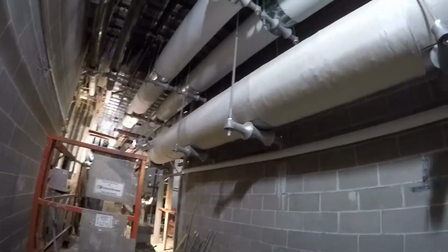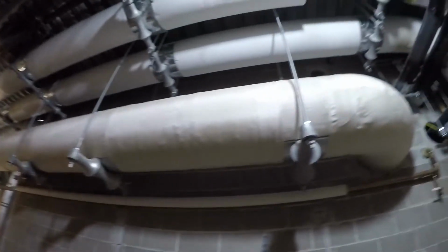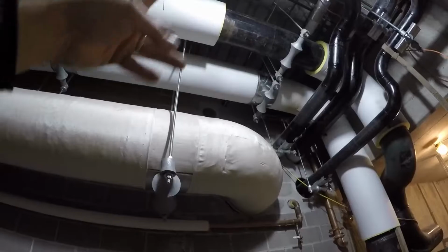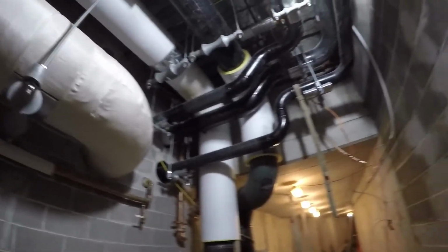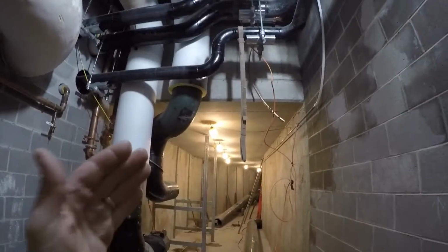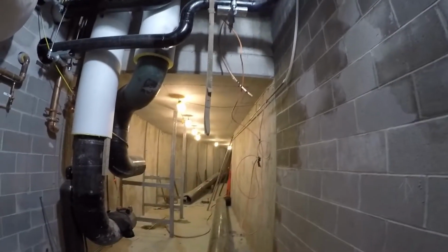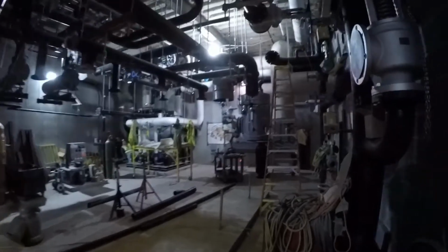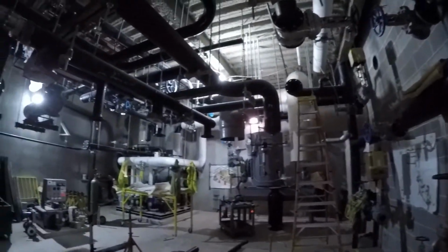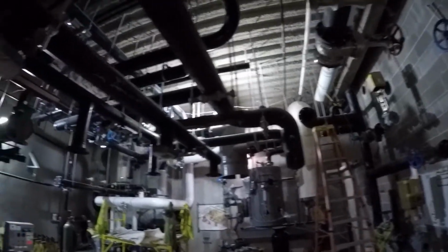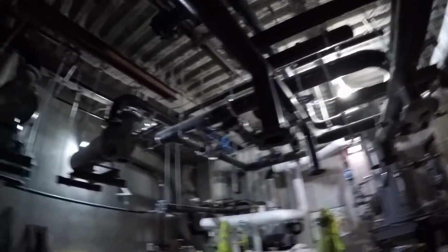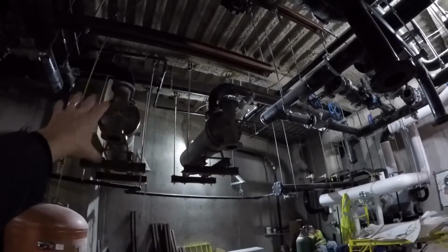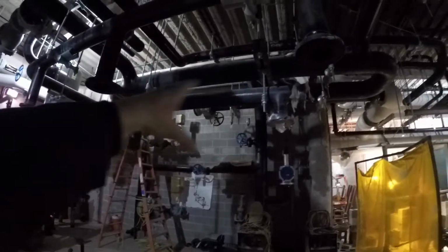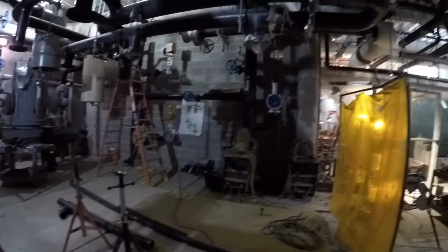Tunnel location in the basement. Looking at the mechanicals here, we have the chilled water supply and return highest up into the ceiling with the steam lines down below, and the utilities are just beginning to run into the new tunnel to tie into the existing tunnel. So we'll stay in the basement and we'll enter the heating side area here. As we talked about before, there's a heating side and then there's a chilled water side through here. So it's great to be able to see all the pipe assemblies up into the ceiling. We're looking at the 2 steam to hot water exchangers over here. None of the circulation pumps have been installed. They'll come off of these headers and down into this location over here.